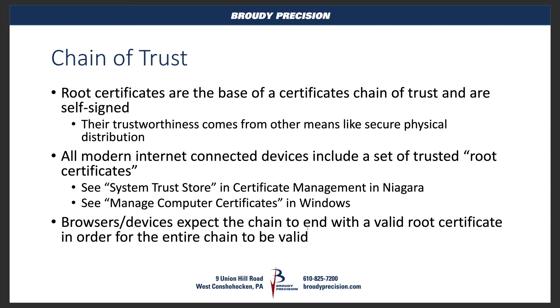Browsers and devices expect your entire chain to be valid, and the key to that is that the root certificate is valid in that chain. So when you open up a connection to a Niagara station and it's using its self-signed certificate that came out of the box, that certificate is not valid because it's self-signed and isn't in the end user's trust store. We'll talk about how we get around that and how we make our certificates valid and trusted. For now, it's good to know what the chain of trust is and why it's trusted by your end device.